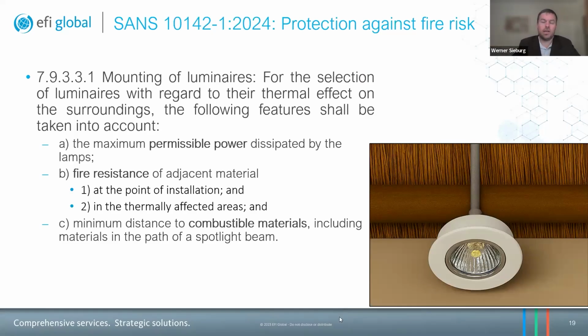And then also number C, and now we're working downwards. The minimum distance to combustible materials, including materials in the path of the spotlight beam. So this is not necessarily a spotlight, it's more of a floodlight where the light disperses from the lamp. But for example, if thatch were to be placed below the lamp, where the radiated heat from the illumination could reach that thatch and could possibly cause hazardous heating, that would certainly have to be considered. And so basically one needs to do a rational design and take all precautions to prevent the outcome of a fire occurring. Okay, thank you, Kashan.